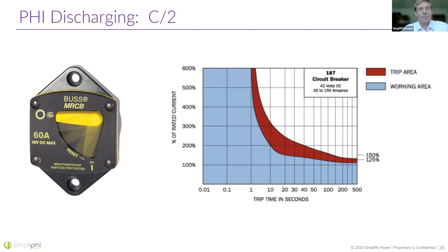And right, the more current you put in, the faster it'll trip. But you can see that at 125%, so somewhere around 75 amps, this thing could take up to 9 minutes to heat up and trip. And then this breaker is claiming to trip much faster right at the 100% mark. But unless you exceed the 125% mark, it could also take a longer time, up to 9 or 10 minutes, 500 seconds there in order to trip.